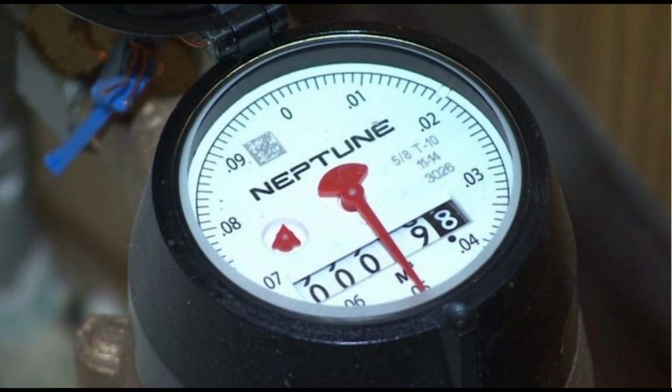Fire meters are a specialized type of turbine meter meeting the high flow rate requirements for fire protection. They are often approved by Underwriters' Laboratories, UL, or Factory Mutual, FM, for use in fire protection. Fire hydrant meters are a specialized type of portable turbine meter attached to a fire hydrant to measure water flowing out of the hydrant. The meters are normally made of aluminium to keep their weight low and usually have a 3 in, 76 mm, capacity.